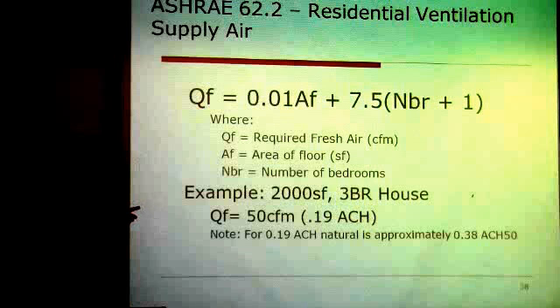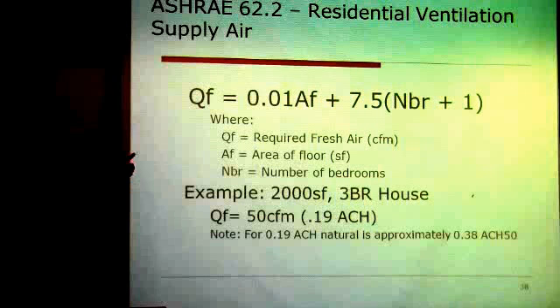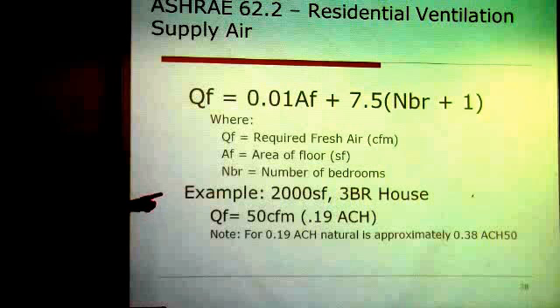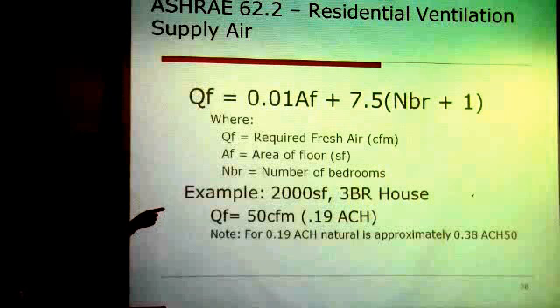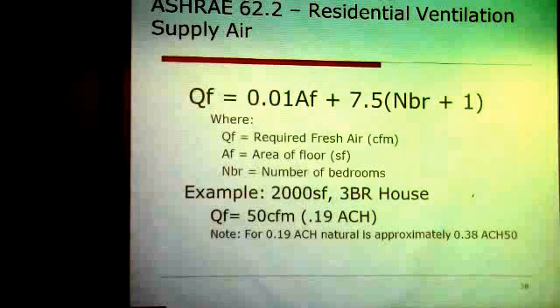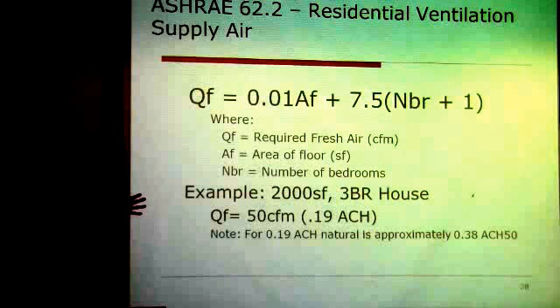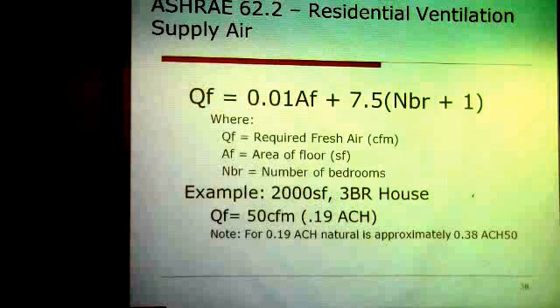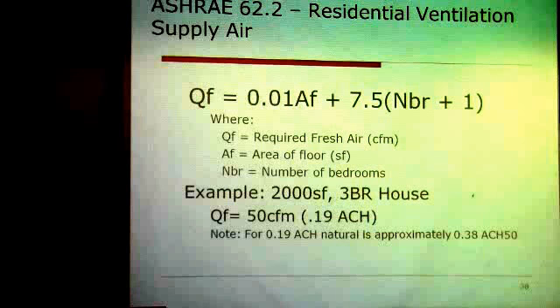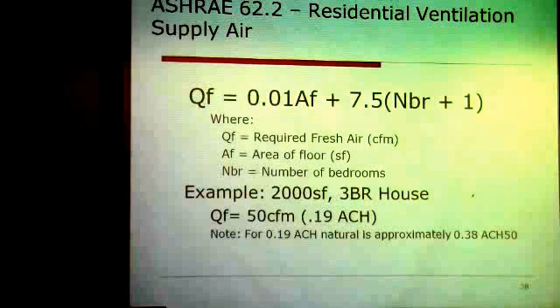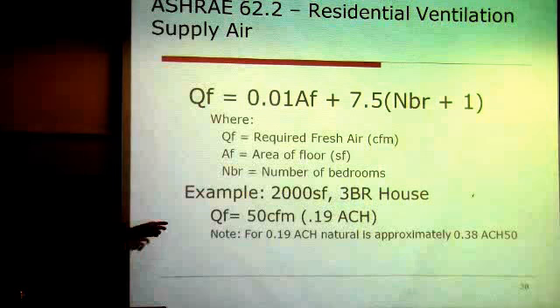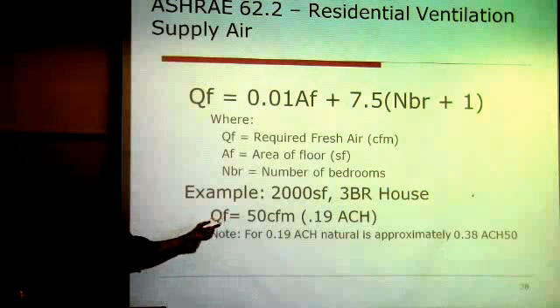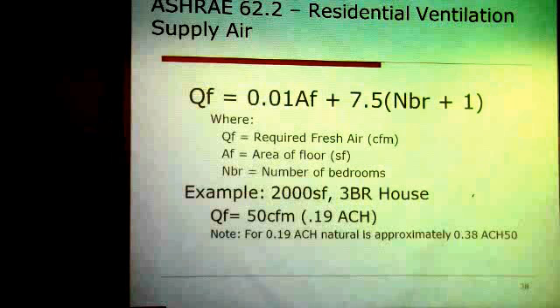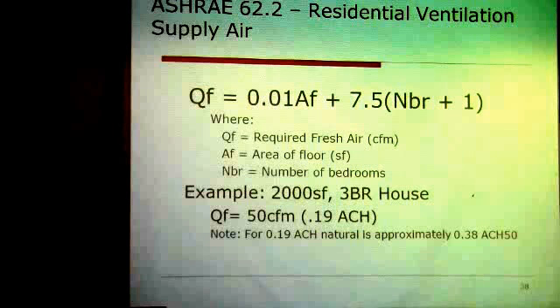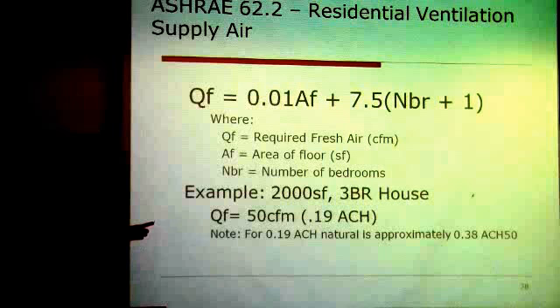If you multiply that out, I did an example of 2,000 square feet. So it'd be 0.01 times 2,000. And if it's a 3-bedroom house, that plus 1 assumes there's 2 people in 1 bedroom. So there's 2 people in a master bedroom plus 2 other bedrooms with 1 person. So it assumes 4 people, and then they assume 7.5 CFM of fresh air per person, and then a little bit extra for the square footage. So in this example, the minimum would be 50 CFM of constantly supplied fresh air, and that's what the building department makes sure it has.